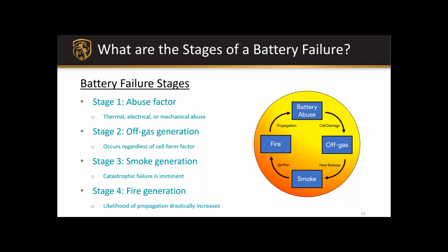The first stage we identify is battery abuse. This is something that will eventually lead the cell into thermal runaway. It can be thermal, electrical, or mechanical abuse. What begins to happen is you get some cell damage, and mechanisms begin to operate inside the cell that lead to increased pressure, which eventually leads to stage 2, the off-gas event.